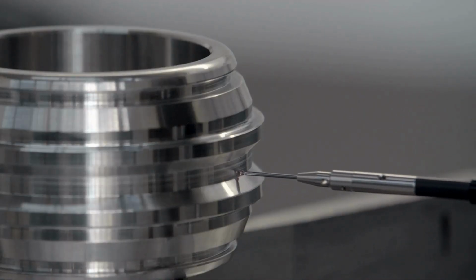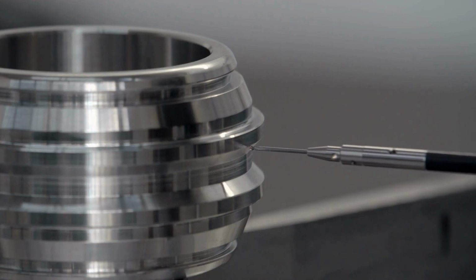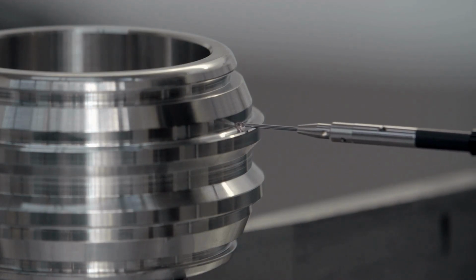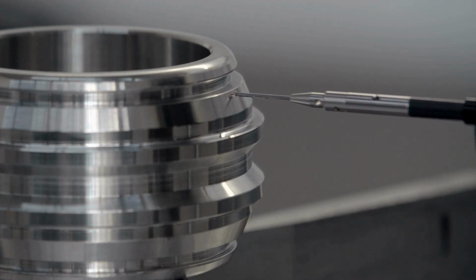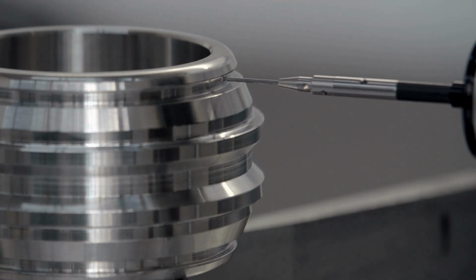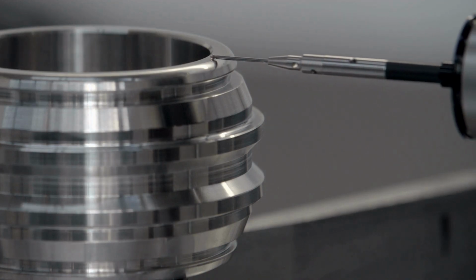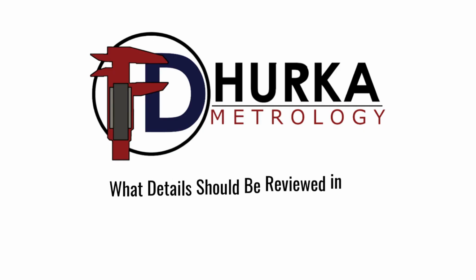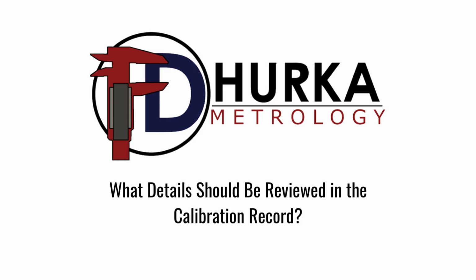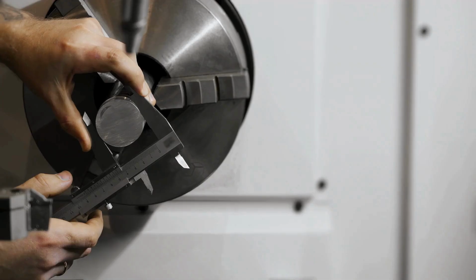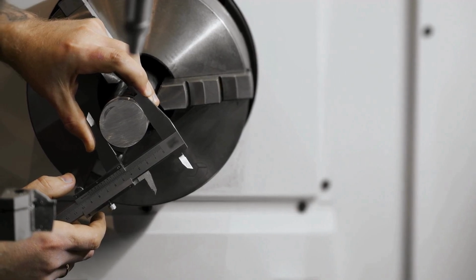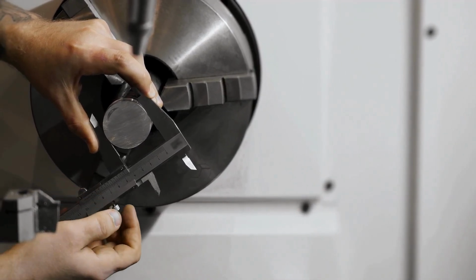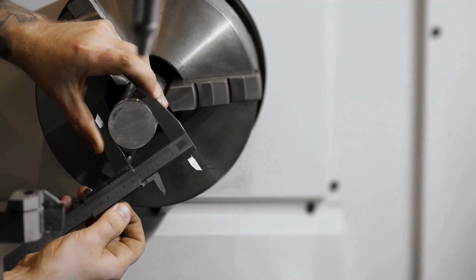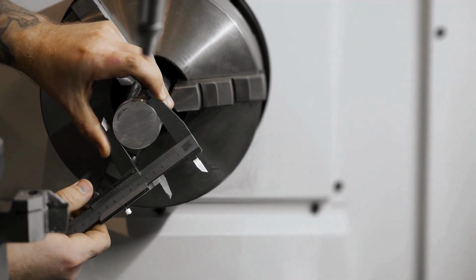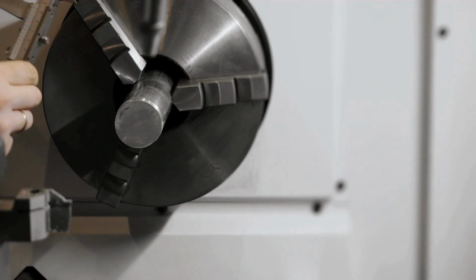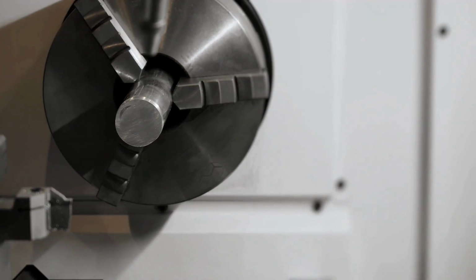A failed calibration procedure helps determine what to do with the tool, how to document the problem, whether earlier measurements may have been affected, and what corrective action is needed before the tool can return to service. What details should be reviewed in the calibration record? The record should include the tool identification, calibration date, who performed the calibration, the acceptance limits, where the failure occurred, whether an adjustment was attempted, and the post-adjustment status.